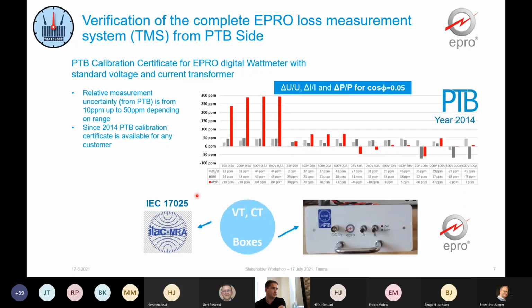And since then, from the first calibration at PTB in year 2014, we offer the customers a fully calibrated system, while EPRO is doing the 17025 calibration on the VTs and CTs, and the measuring boxes calibration on the PTB primary power standard in Braunschweig. As you could see in our prospect, we tend to round our accuracy to 1000 ppm or 0.1% for power measurement at power factor of 0.05, although the accuracy is better than that. The reason here is simply to provide a better guarantee in more and more important loss measurement.